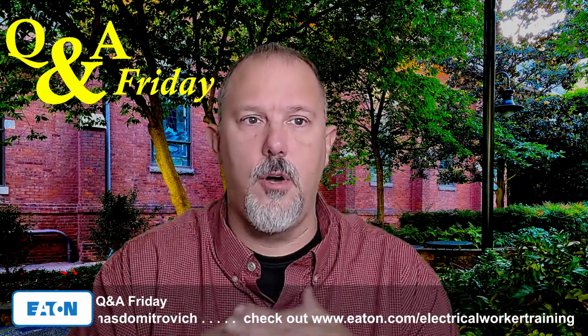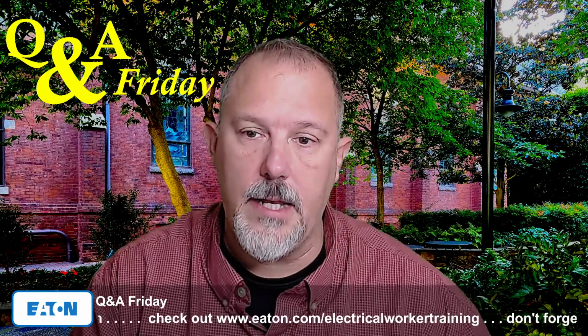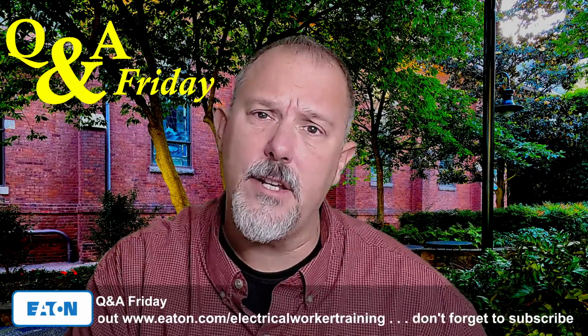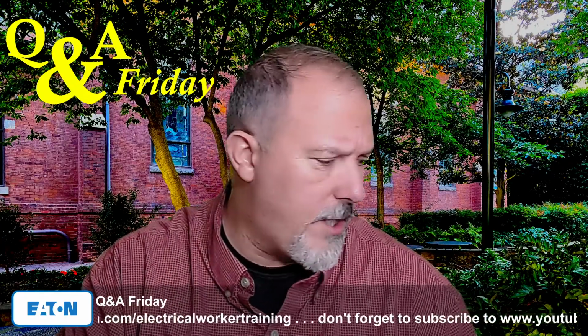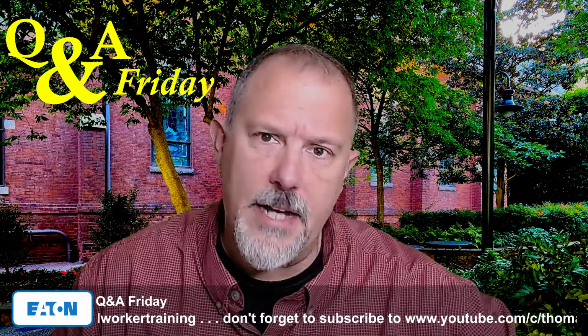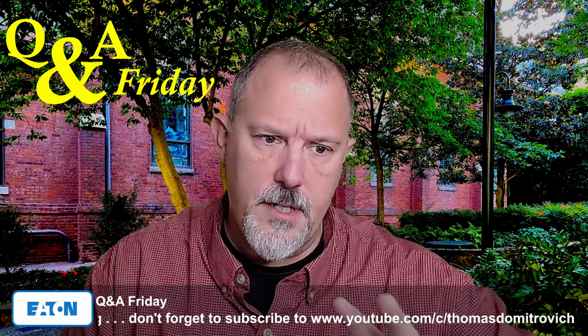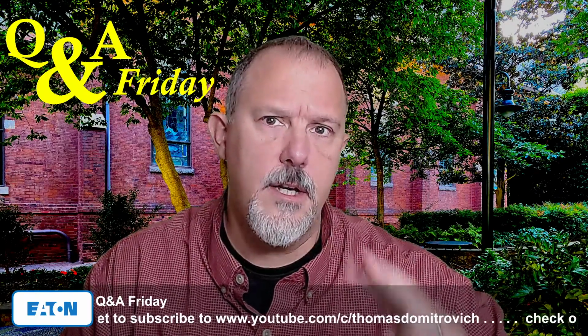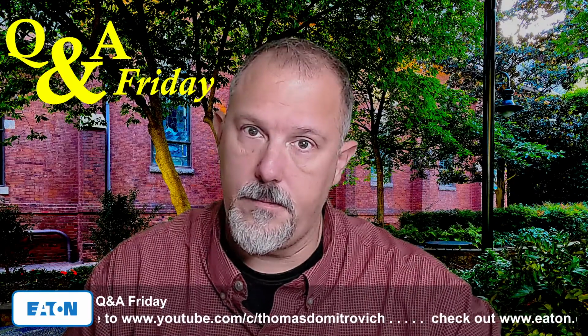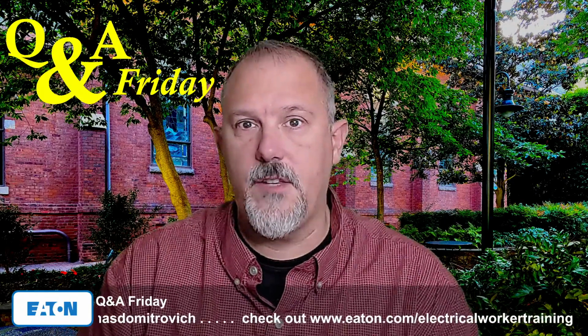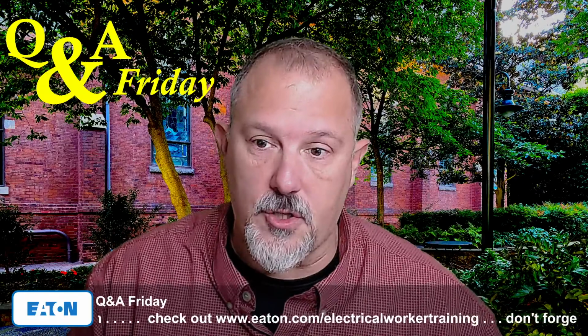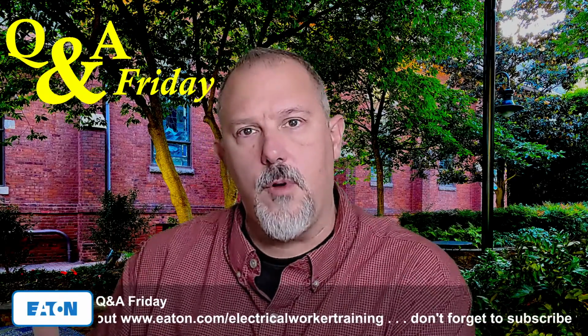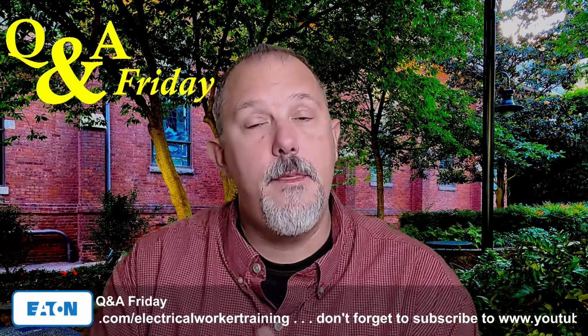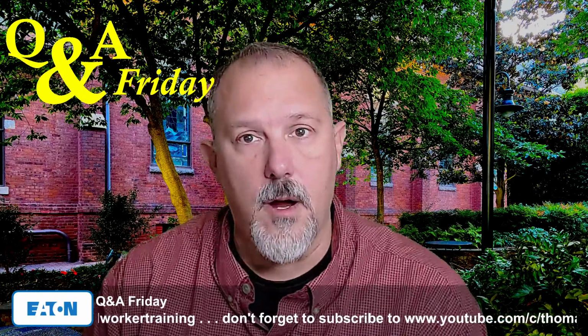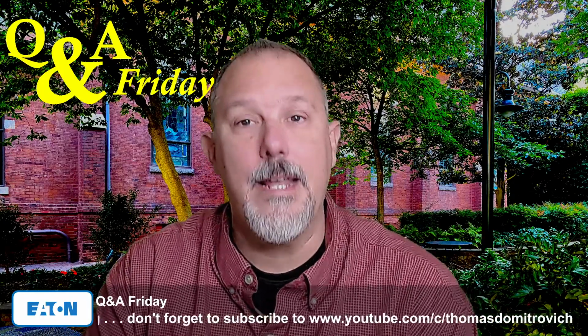I went through all of the different areas in the National Electrical Code that are impacted, trying to address two key words. If you think about arc flash and incident energy, two things you got to worry about are severity and likelihood. From an arc flash perspective, severity is measured in calories per centimeter squared. So my presentation looked at the code requirements that help reduce the severity of an event, and then the code requirements that help reduce the likelihood.